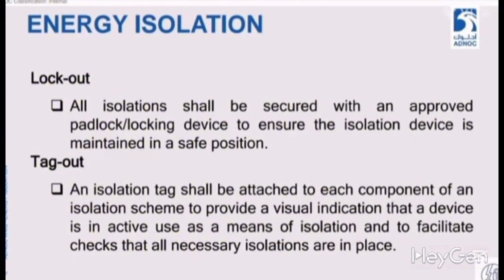Along with this, the most important thing is that when placing a lock, we must also display a tag there which should have all the relevant information mentioned on it. There is a visual identification that this device has been locked, for what purpose, under which permit, and for how long the energy is expected to remain isolated. Who is the authorized person to come and restore it, so that this can be double checked and ensured that no unauthorized person restores the energy during the activity.